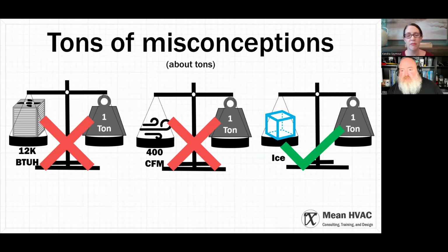A ton refers to how much heat it takes to melt a ton of ice over the course of a day. Back when we used ice-melting systems in the 1800s, you would size systems by tons of ice. At a certain point we created refrigerant-based cooling, and we still sized them that way, because tons per day became BTUs per hour. If you do the math, it works out to about 11,900 and change, so we call it 12,000. But we don't use ice in modern heating and cooling, right?